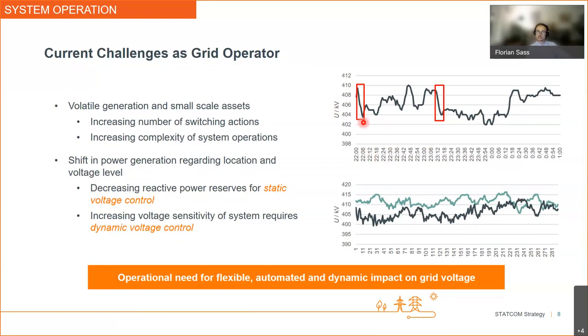This is some historical data measured between 10 p.m. and 1 a.m. This is the voltage measured in one of our substations in such a high transit area. And as you can see, we have some severe voltage dips and voltage jumps of about 4 to 6 kV. So this means the system is right now highly sensitive towards active power changes and reactive power changes. So we are really facing an increased voltage sensitivity, which is a thing.